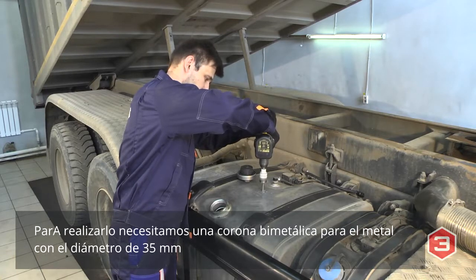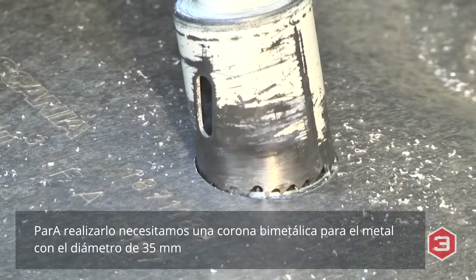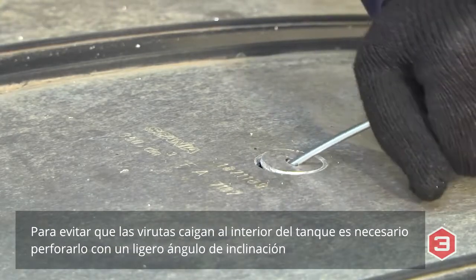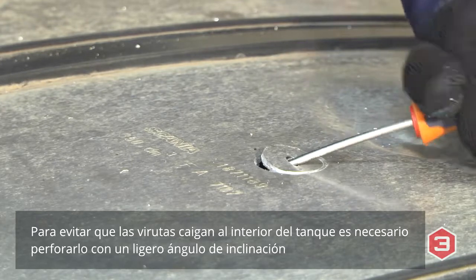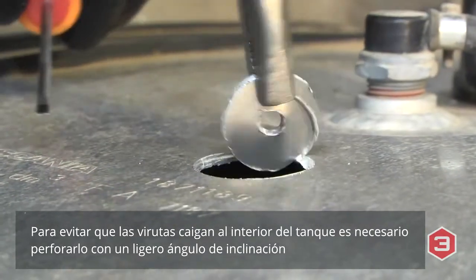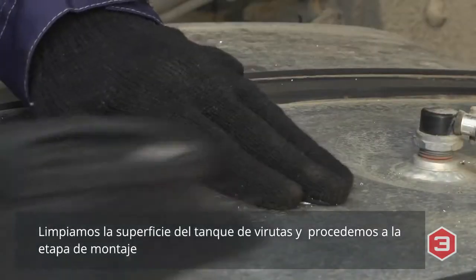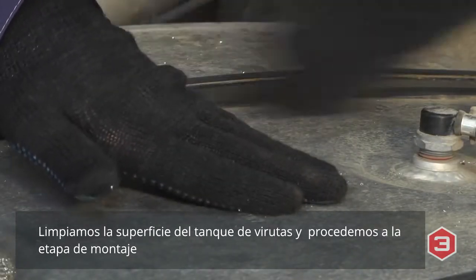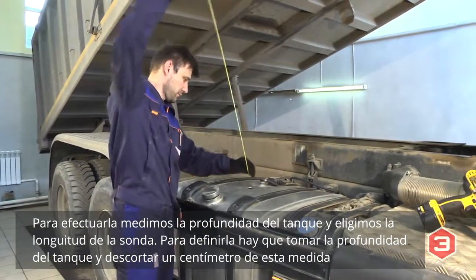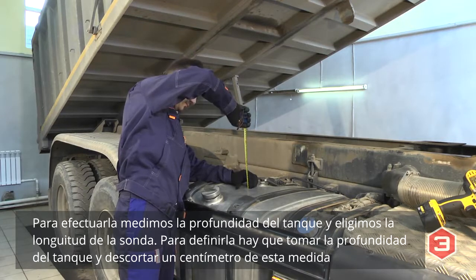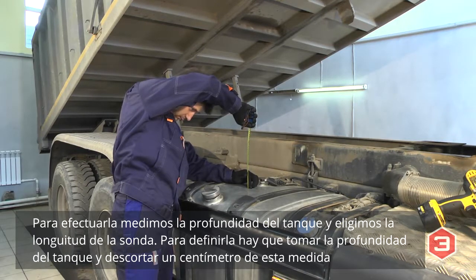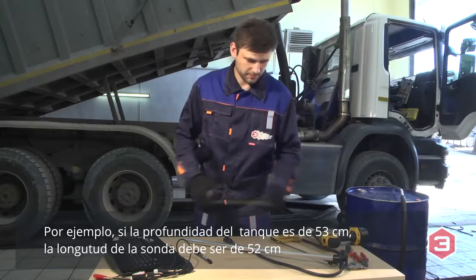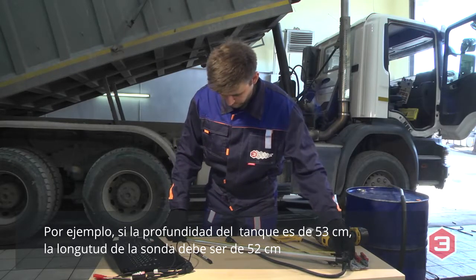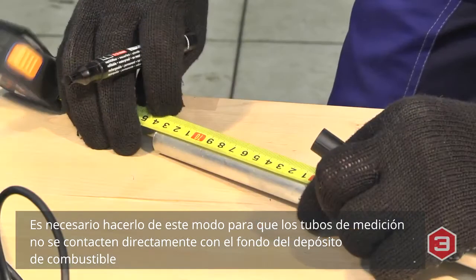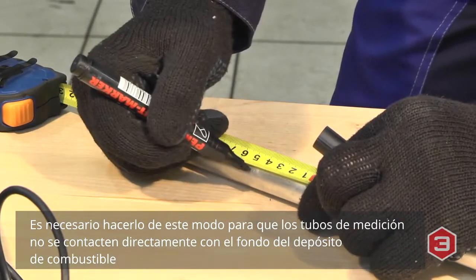You will need a 35 mm diameter bimetal core bit to drill a hole for installing the sensor. Keep the drill slightly inclined to prevent metal chips from falling inside the tank. Clean the tank surface of metal chips and proceed to the next step. Measure the tank depth and then measure off the sensor length according to the tank depth minus 1 cm from its bottom. For instance, if the tank depth is 53 cm, measure 52 cm of the sensor. It is necessary to do so the measuring tubes don't touch the tank bottom.